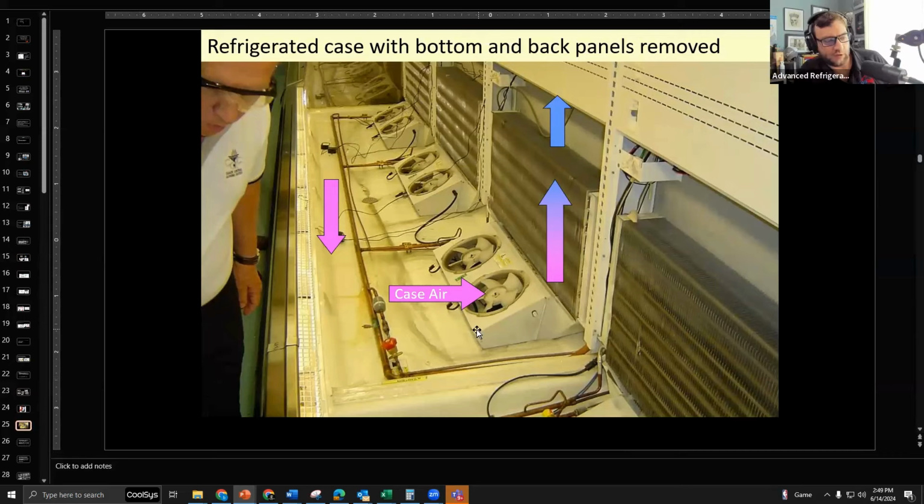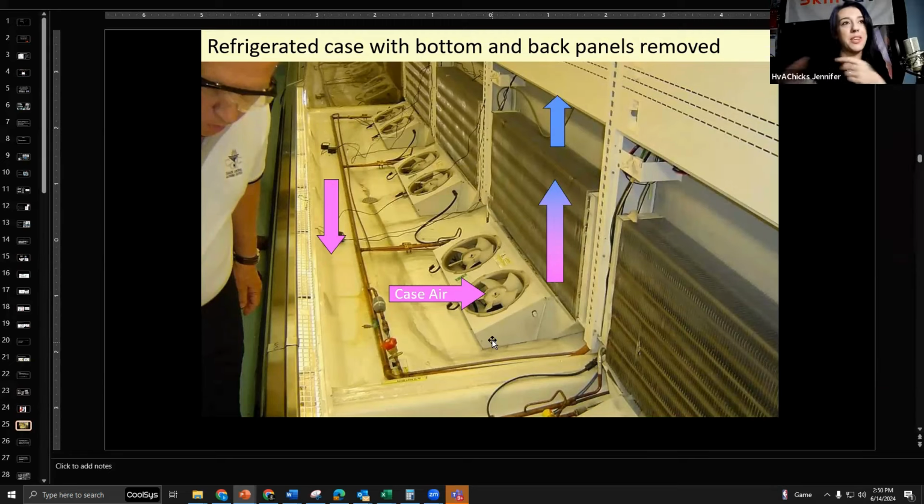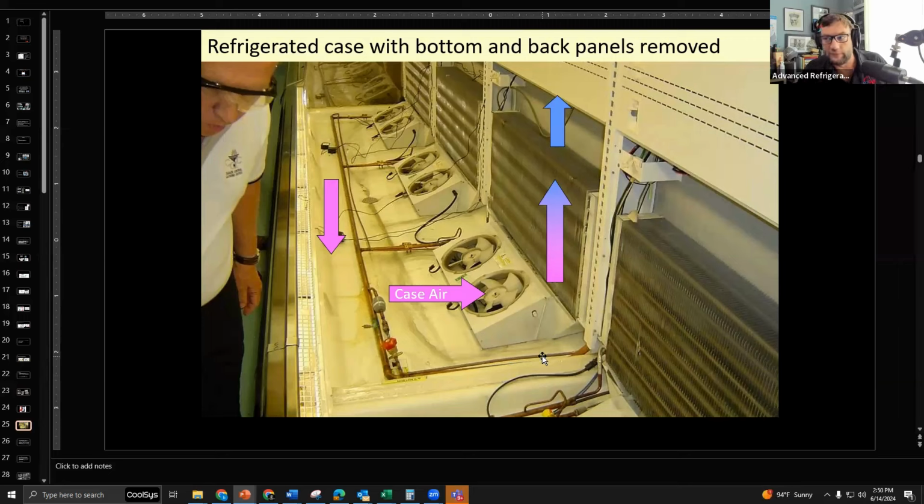So once again, making sure we have the proper airflow. Now you do need to make sure that, with evaporators like this, the plenum is actually all the way down. It's very easy to assume that, oh, it looks like it's down or the airflow is good. And I'll get into why good isn't a form of measurement.